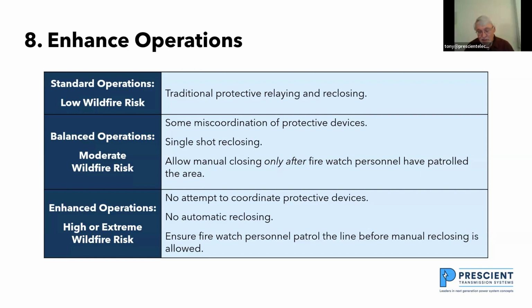And then I explained to the utility what I was recommending they do. And they explained to me that maybe we should only use 3 setting groups. And that's how we got to 3 setting groups like this. And then we were trying to see how do you name them? The way balance came up is we're taking a balance between optimizing our performance indicators and reducing our fire risk. Enhanced operation just means that we've got a high fire risk at that point.